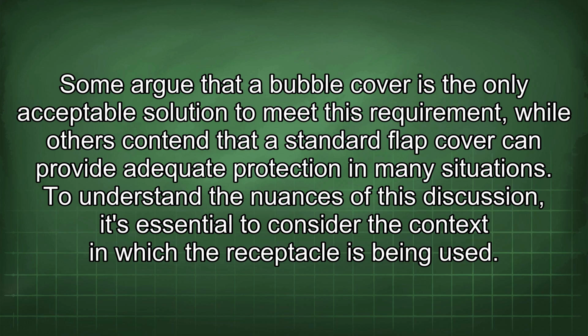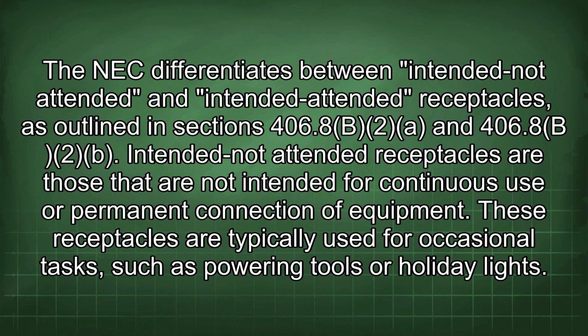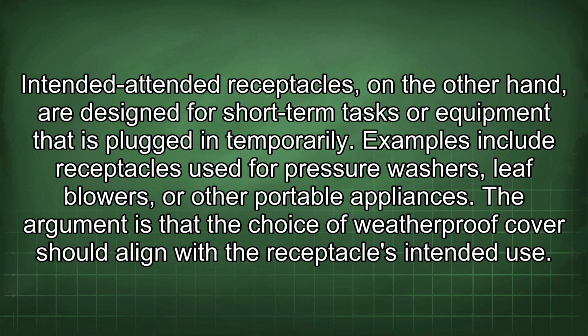To understand the nuances of this discussion, it's essential to consider the context in which the receptacle is being used. The NEC differentiates between intended not attended and intended attended receptacles as outlined in sections 406.8(B)(2)(a) and 406.8(B)(2)(b). The intended not attended receptacles are those that are not intended for continuous use or permanent connection of equipment. These receptacles are typically used for occasional tasks such as powering tools or holiday lights. Intended attended receptacles, on the other hand, are designed for short-term tasks or equipment that is plugged in temporarily.